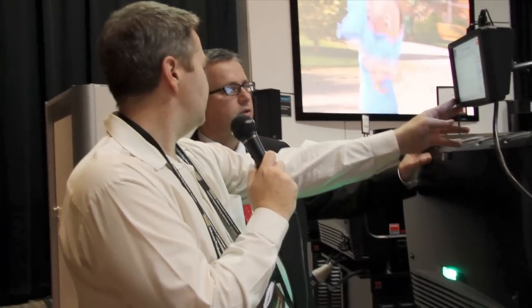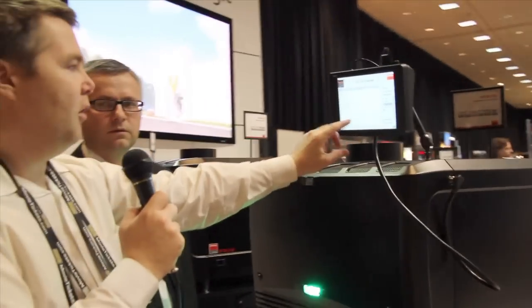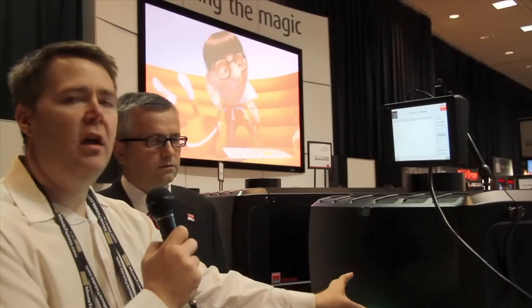You were showing me this new diagnostic screen specifically for the operator. We call it the diagnostic companion — it's basically an additional tool to help service our equipment. Instead of just showing errors and leaving operators wondering what the problem is, the operator can click on an icon which walks them through visual steps on how to troubleshoot, pointing directly to where the problem occurs. When a problem occurs, it comes up on screen with a picture directing you to exactly where to look and what to rectify.